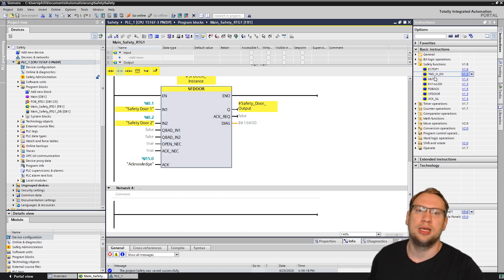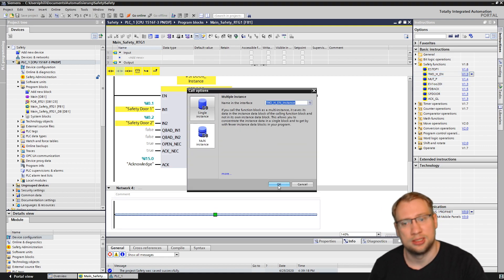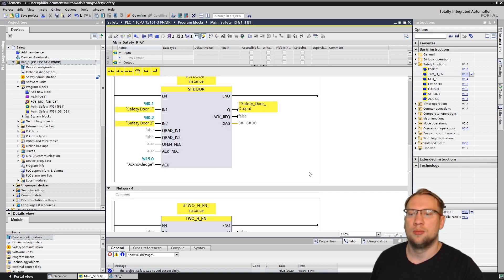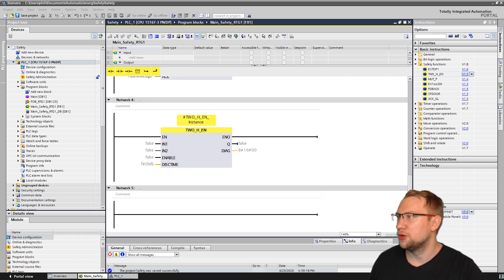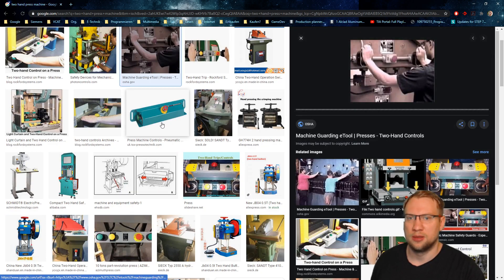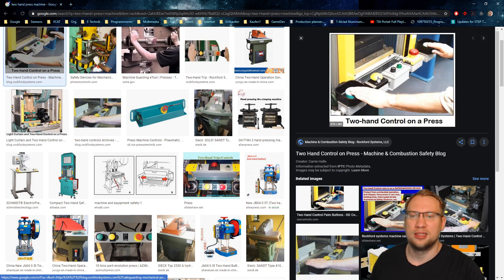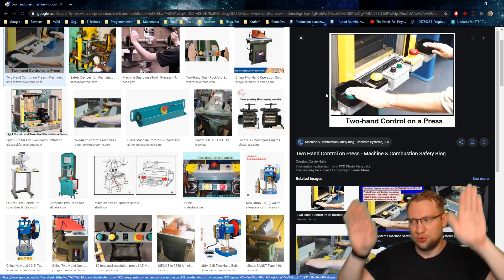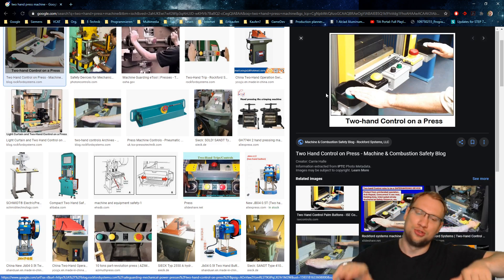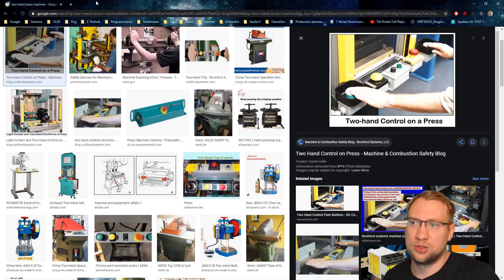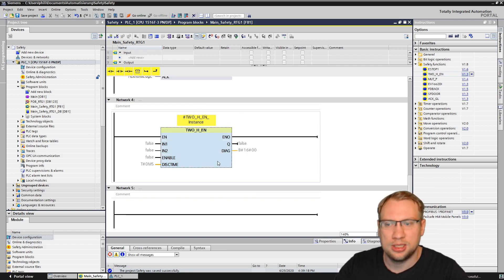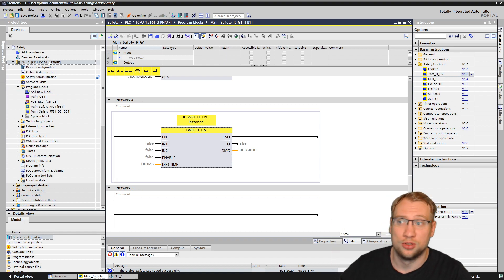The next block is a two-hand press. I'll put that in here and take a multi-instance again so we can find the data block in our parameters. For those who don't know it: a two-hand press basically means you have two buttons to start a process. You have to press both buttons because you have two hands, so you cannot activate it with one hand while the other hand is still in the machine. That's why we have two-hand presses, and of course they are safety devices that need special safety treatment — exactly what this block provides.